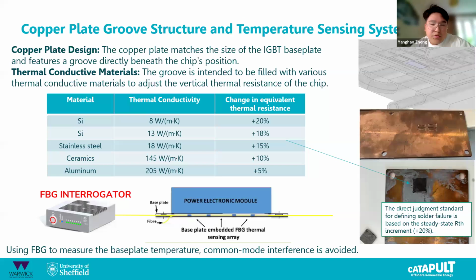To design the module with different thermal resistance states, we created an additional copper base plate. The thermal resistance can be adjusted by changing the thermal interface material under the chip. The copper plate matches the size of the IGBT base plate and has a groove beneath the chip. These grooves hold different thermal conductive materials, so as to adjust the vertical thermal resistance. The range is from 5% to 20%, because the direct judgment standard for defining solder failure is based on a steady thermal resistance increment of 20%. Additionally, a through channel below the groove allows for the placement of a fiber optic temperature sensor to monitor the base plate temperature.